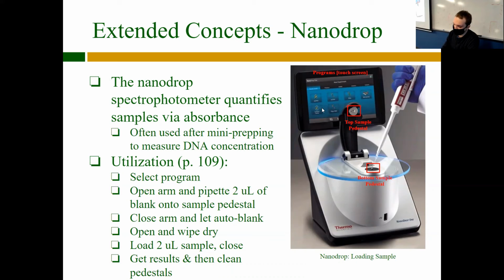There'll also be a big graph. Typically, I think you're looking for a bell curve. If it's not a bell curve or it goes into the negative territory, most likely your sample is either highly contaminated or there's nothing in it. Likewise, it's going to give your DNA readings in nanograms per microliter. If your reading's like 2 nanograms per microliter, that means it didn't really work. Your mini prep didn't work. You're typically looking for at least, I'd say, 40 or 50 nanograms per microliter.